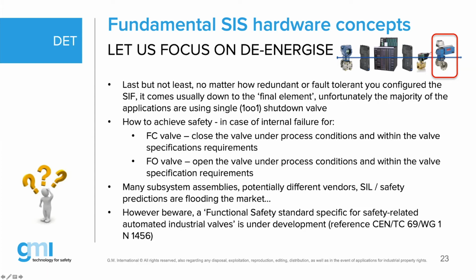And then you come into the final elements, and they go from redundant channels, from redundant input, redundant voting, redundant logic, redundant relays, they go to one single final element. Because the thing is, they said the final element cost too much money and we could not install 2 valves. We were only allowed to install 1 valve. So then you can ask yourself the question, does it make sense for us to build everything redundant all the way up to the final element when I still keep on maintaining a single element at the end of our safety loop?